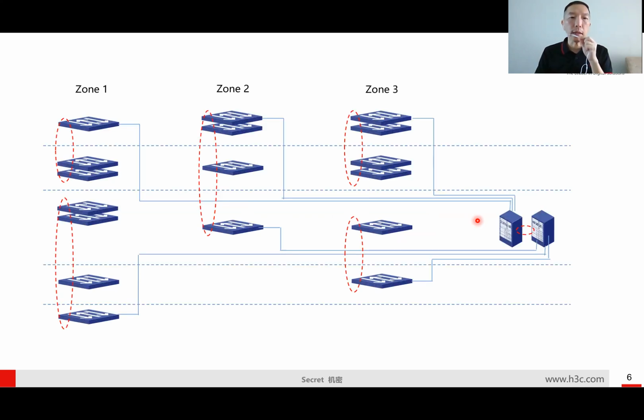So what it looks like, you see here, in the beginning of the design, they had 7 units of switches. Then, because we can take advantage of the same vertical trunk to put short distance multi-mode fiber to link all the switches together, I can break it into 2 rings. In Zone 3, I can also put it into 2 rings. So that means we only need to add extra fiber to the core at 2 locations.